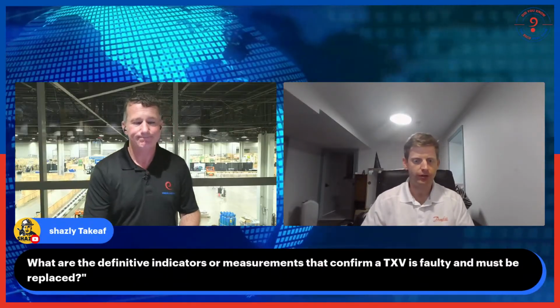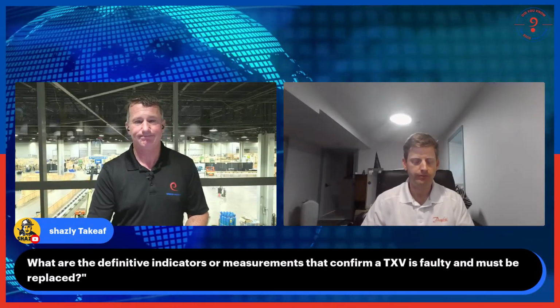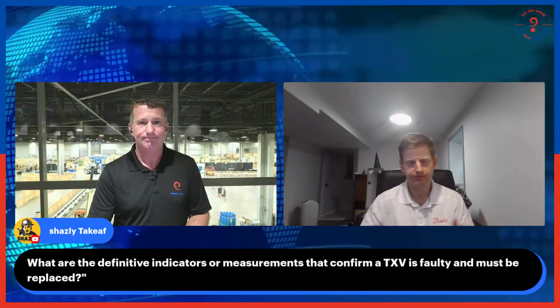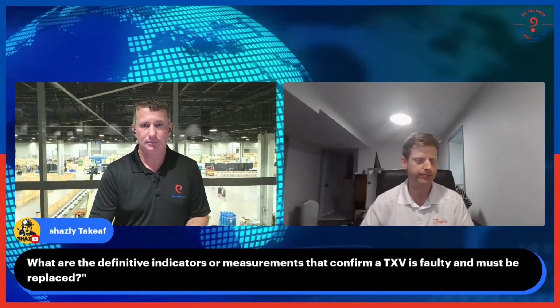Yeah, I mean, what indicators? Superheat being off is the first one, but you then have to go verify. Well, if the superheat's off, but the subcooling's near zero as well, fix the subcooling and then see if that fixes the superheat. It kind of has to be a process of elimination, and when it comes to contaminants blocking up a TXV.